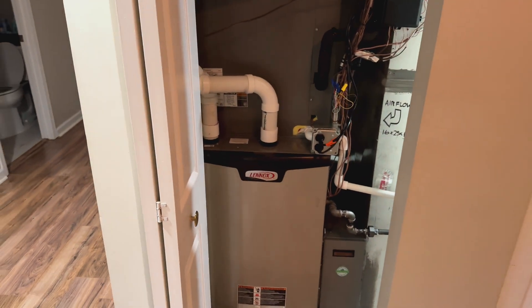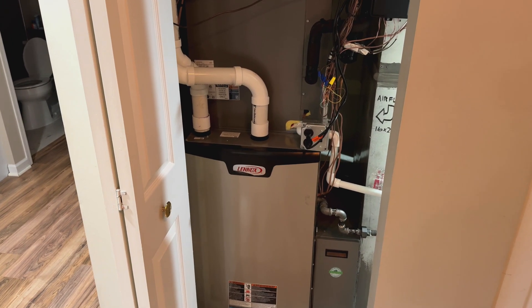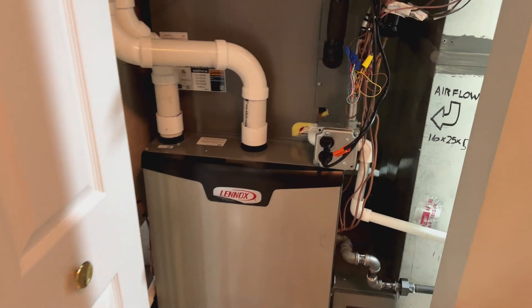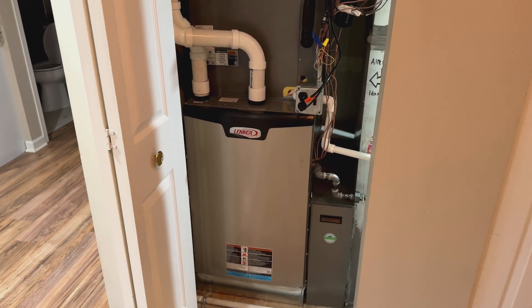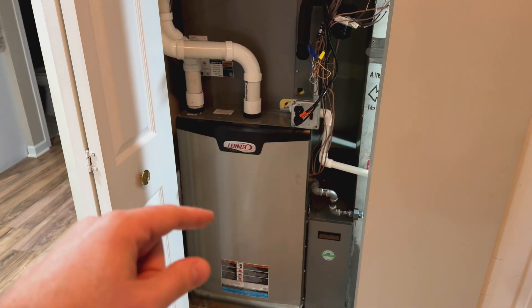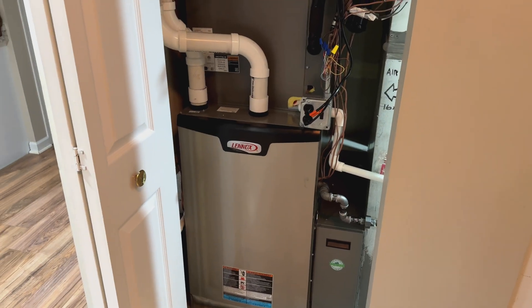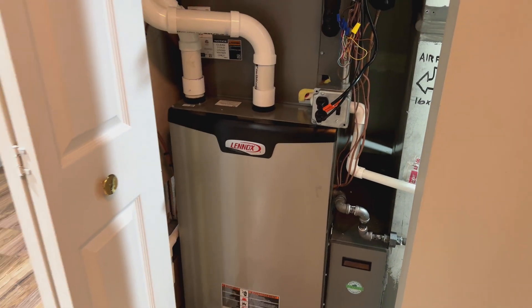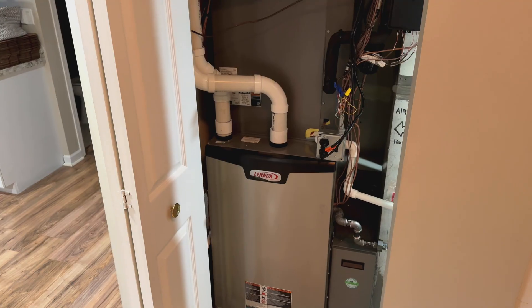Here is the indoor portion of the equipment. We have our Lennox gas furnace — it's an SLP99. It's variable capacity, similar concept to the outdoor unit. What that means is this furnace can adjust its heating capacity — the flame can change sizes from very small to maximum in 1% increments, depending on how much heat is needed. It also has a variable speed blower that constantly adjusts its speed. And it's communicating, controlled by the same system.